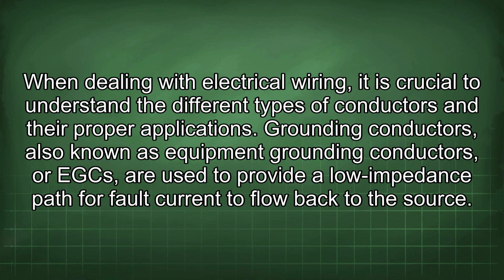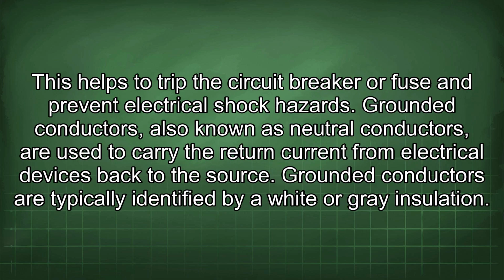Grounding conductors, also known as equipment grounding conductors, or EGCs, are used to provide a lower impedance path for fault current to flow back to the source. This helps to trip the circuit breaker or fuse and prevent electrical shock hazards.